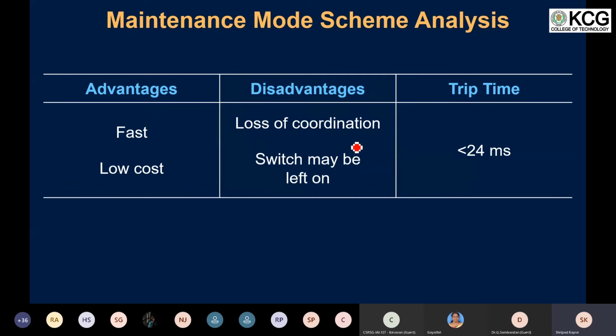And there are even chances that the operator may leave the relay in maintenance mode even after the work is done. So there is a chance of human errors along with the other issues related to the loss of coordination. And also sometimes this kind of switching is done on a network based protocol. So there is even a threat related to cyber security coming into the picture. And if you look at the overall operating time, it is somewhat close to 20 to 30 milliseconds even here.